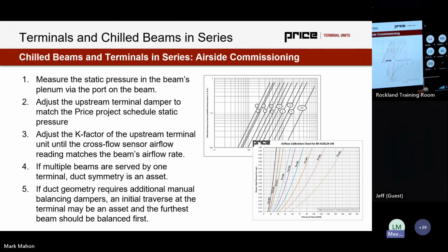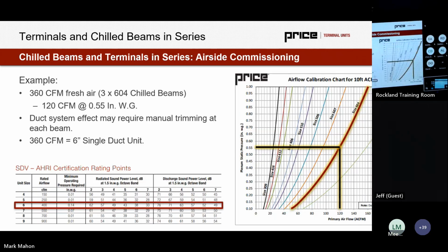Then the other thing I'd note too, if duct geometry requires additional balancing dampers, which it often will with this type of system, one VAV serving a zone, two chilled beams, one's a little bit further, we're going to need a balancing damper on the closer one. An initial traverse at the terminal is sometimes done just so we can get the airflow close to set point to help with the balancing process downstream. It's going to make that process a lot more simplified and faster to have a good initial checkpoint for our total design airflow rate to the zone.